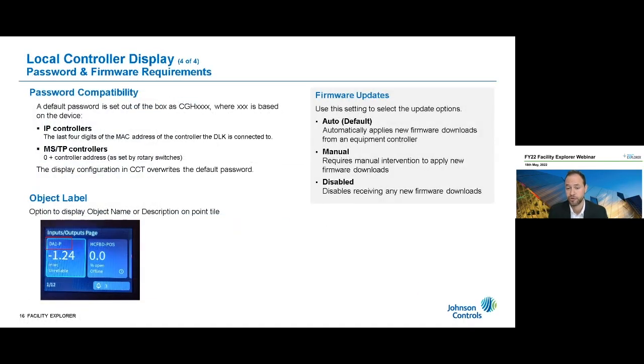The DLK is also password protected. The default password is set as CGHXXXX, or 4 X's. When it comes out of the box, these are the last 4 digits of the MAC address if it's an IP controller, or if it's an MSTP controller, these are the address on the rotary switch. Since there are 3 fields, they would typically start with 0 followed by the 3 digits of the MSTP controller address.